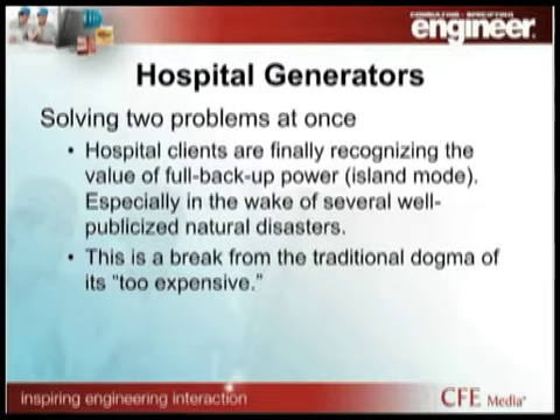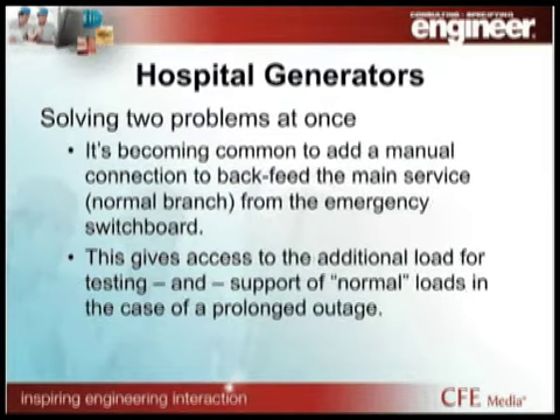Obviously, you can open the main and serve the whole facility, commonly called island mode, and in the wake of several disasters that definitely gives you a real reason to give that facility that mode. It's a break from the traditional dogma. I'm getting requested more and more often: we not only want extra emergency power, we want to power the whole facility off of a generator. Now, a lot of the reason we've been doing this, as opposed to recommending a load bank or another method of testing the generators, is because it gives that client confidence that he can power up his whole facility.